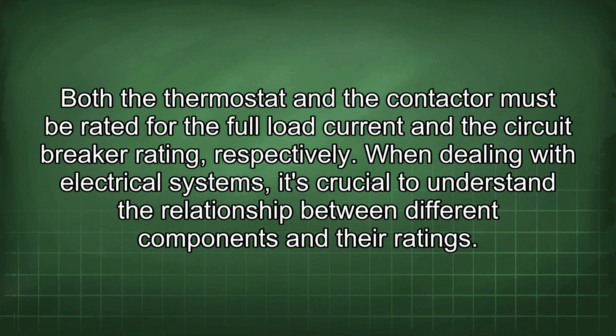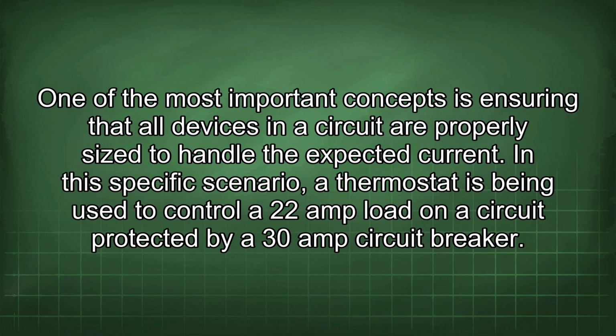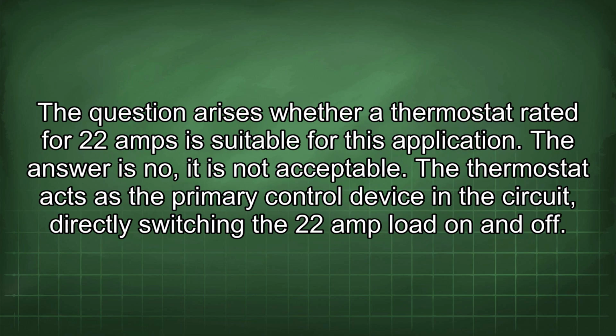When dealing with electrical systems, it's crucial to understand the relationship between different components and their ratings. One of the most important concepts is ensuring that all devices in a circuit are properly sized to handle the expected current. In this specific scenario, a thermostat is being used to control a 22 amp load on a circuit protected by a 30 amp circuit breaker. The question arises whether a thermostat rated for 22 amps is suitable for this application. The answer is no, it is not acceptable.